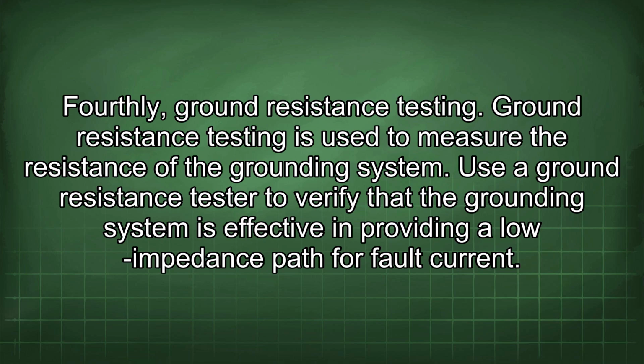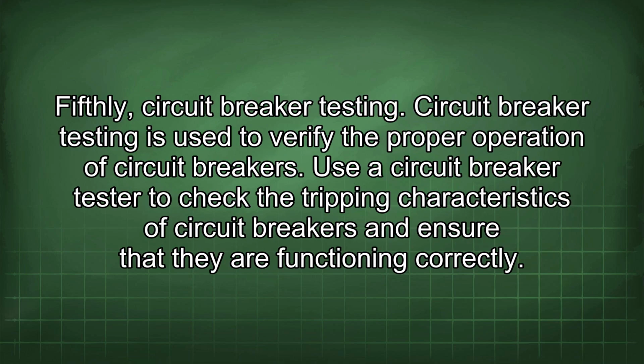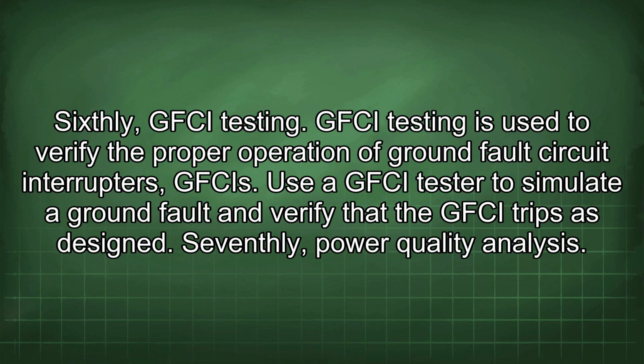Fourthly, ground resistance testing. Ground resistance testing is used to measure the resistance of the grounding system. Use a ground resistance tester to verify that the grounding system is effective in providing a low impedance path for fault current. Fifthly, circuit breaker testing. Circuit breaker testing is used to verify the proper operation of circuit breakers. Use a circuit breaker tester to check the tripping characteristics of circuit breakers and ensure that they are functioning correctly. Sixthly, GFCI testing. GFCI testing is used to verify the proper operation of ground fault circuit interrupters, GFCIs. Use a GFCI tester to simulate the ground fault and verify that the GFCI trips as designed.